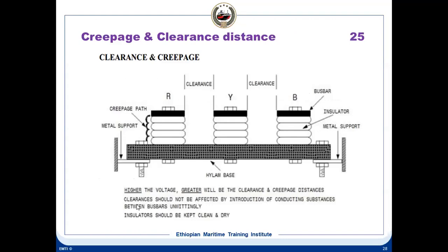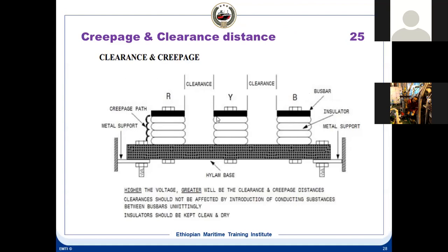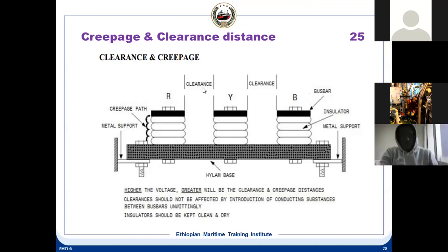Next is the creepage and clearance distance. This is not as simple as it looks. Clearance means the distance in air. You see, these are the three conductors here, three cables, RYB, three-phase cables. The distance in air between R and Y is known as the clearance space.